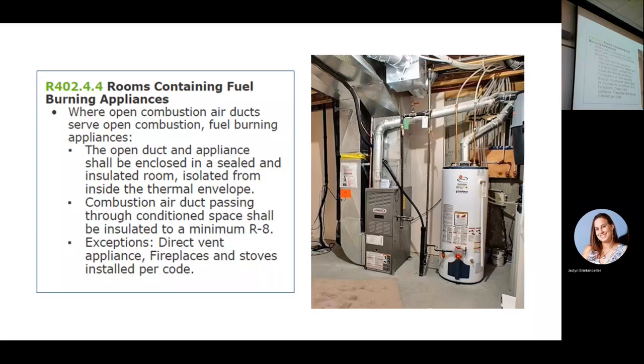So, now I've had people say, well, you know what, 95% efficient furnaces have more problems than 80s, and I disagree. When 90% furnaces first came out it was about 1980, 1981, they did have some issues. And they've been worked out a long time ago. My experience is sealed combustion appliances have fewer problems than open combustion appliances. Those that do HVAC, if you run both pipes on your 95% efficient furnace, so you're drawing combustion air from outside, not drawn from inside, or direct vent water heaters, how many have flame rod problems like you do with 80% efficient furnaces? I never had problems with my direct vent furnaces. I can't even remember cleaning a flame rod on a direct vent furnace. I've cleaned thousands of flame rods on 80% efficient furnaces.